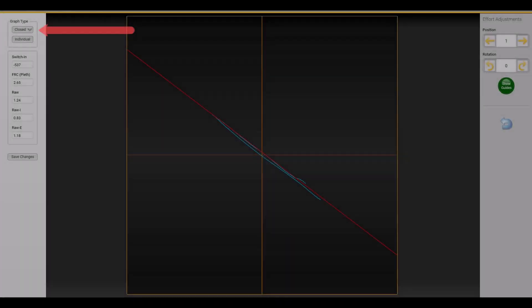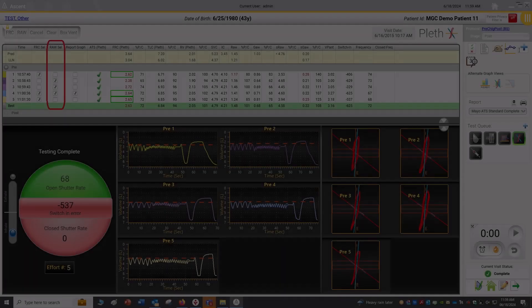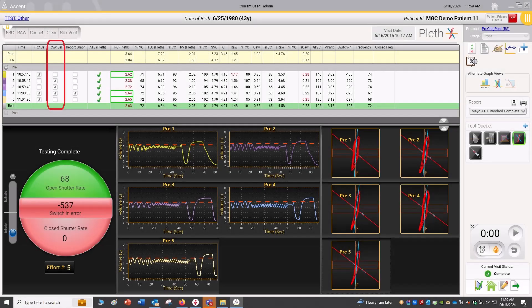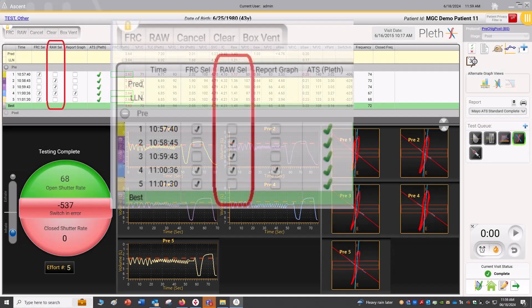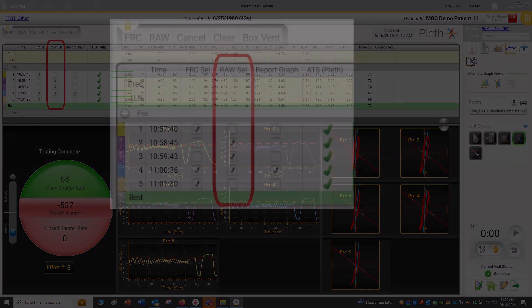To adjust the line of best fit for the closed shutter breathing, select Closed from the drop-down menu in the upper left. This will display the blue tracing — adjust this line the same as the Lung Volume graph. When all adjustments have been made, select the Save Changes button to return to the test screen. Once you are satisfied with the line of best fit for all efforts, select the airway resistance efforts you wish to average for the final report.